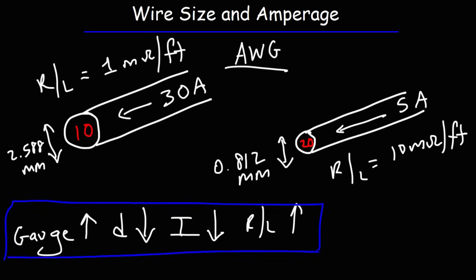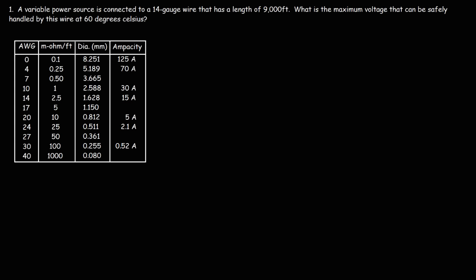To summarize: as the gauge number increases, the diameter size decreases, the amount of current it can handle decreases, but the resistance increases. Here we have a table that lists the wire gauge, the resistance per unit length, the diameter size, and the ampacity — the maximum current the wire can handle at 60 degrees Celsius.